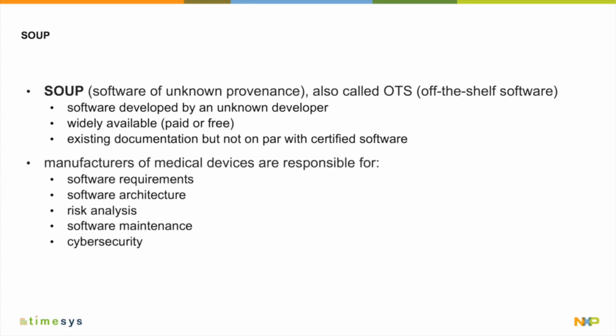create software requirements, define software architecture, do a risk analysis, plan for software maintenance, and how they are going to address the cybersecurity. So when working with open source, in case of medical market, the device manufacturer needs to create this SOUP document that captures a lot of that information, and it helps track also the software that's being used in products.